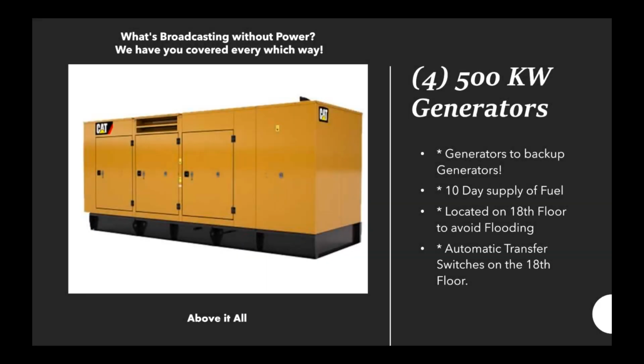Now let's talk about generators. We'll have four 500 kW generators in the building, located on the 18th floor to avoid flooding, like what happened at the Willis Tower a couple of years ago when a flood knocked out power to their generators at the top. Ours will be on the 18th floor — four 500 kW units, with automatic transfer switches also on the 18th floor. There are four generators because we can actually operate on just two 500 kW generators.